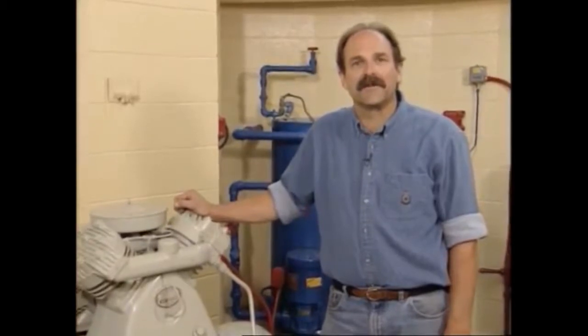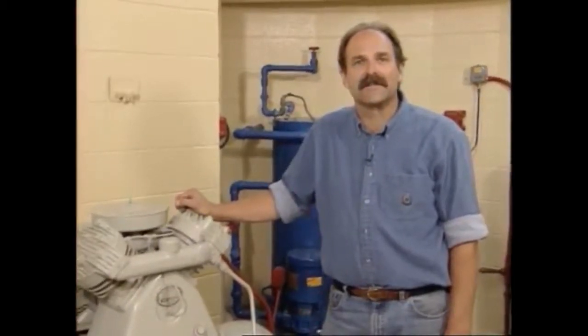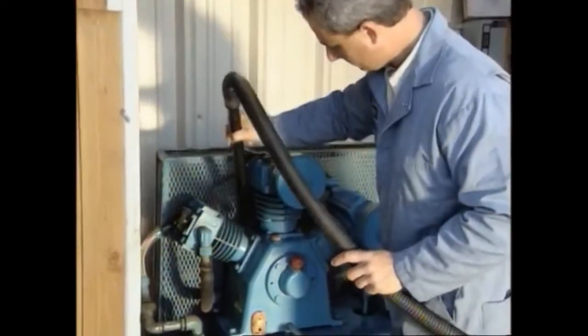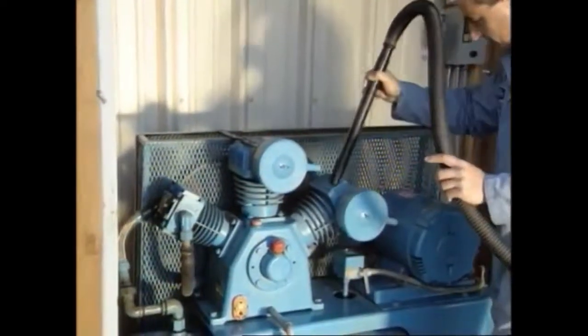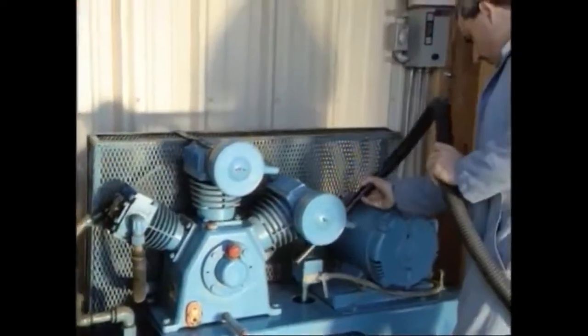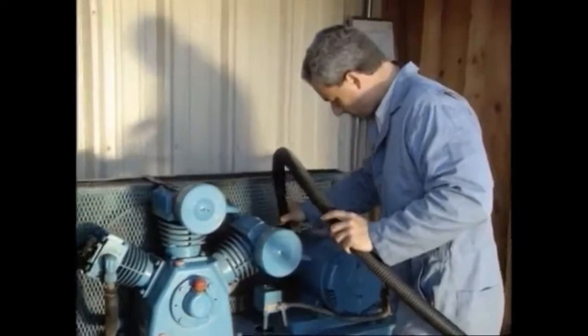If it is equipped with a filter, this should also be changed. Cylinder or casing fins should be cleaned weekly with compressed air or vacuumed off. The fins must be cleaned to ensure proper cooling of the compressor. To have proper lubrication, you must first set up a lubrication schedule. This could be a simple card system, checkoff sheet, or elaborate computer system.